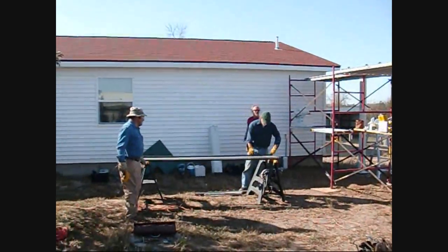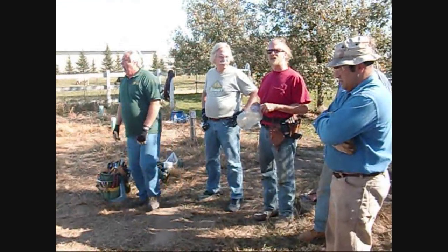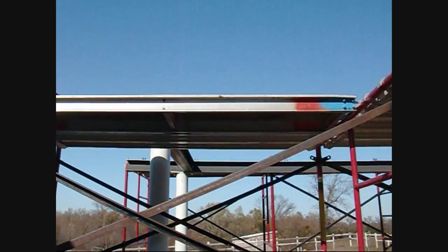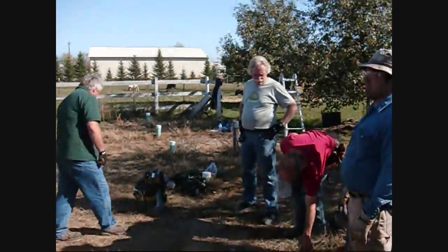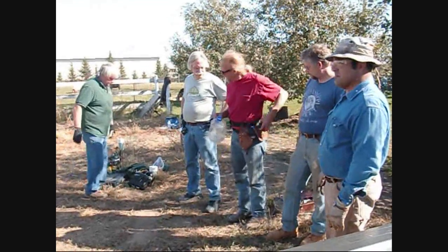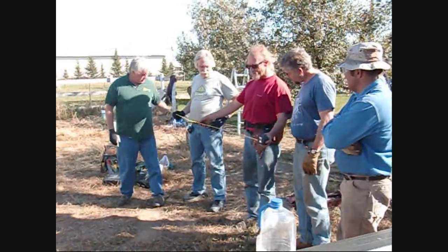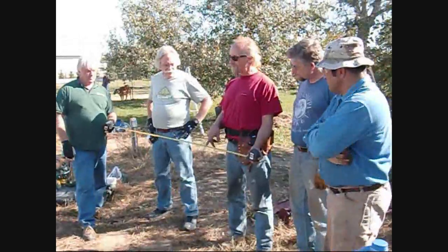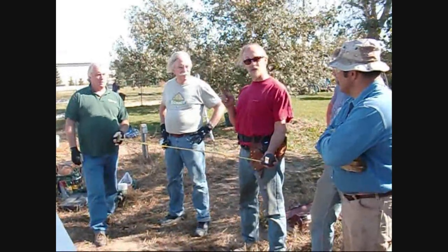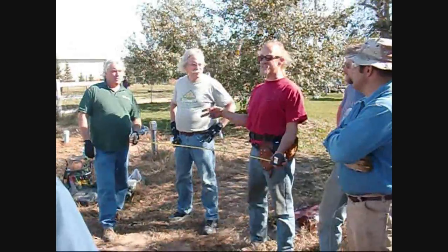This is where you start — we'll start from one end. If you start on very long rows like this, it makes a difference where you start, and in this one we could start in the middle. There's a center line to these beams. A handy dimension: we were laying out a 40-panel job in Falcon Heights, and when measuring across 10 panels center-to-center on the unions connecting these panels, the dimension is 50 and one half inches. This holds true for a row of at least 10 panels within a quarter inch. So I have marked my tape measures when I do these layouts.